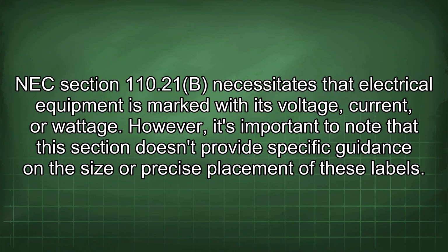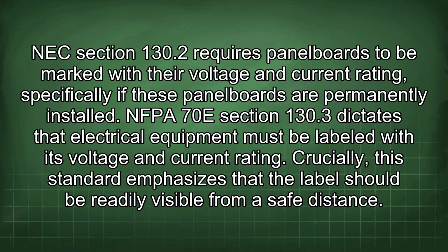NEC Section 110.21b necessitates that electrical equipment is marked with its voltage, current, or wattage. However, it's important to note that this section doesn't provide specific guidance on the size or precise placement of these labels. NEC Section 130.2 requires panel boards to be marked with their voltage and current rating, specifically if these panel boards are permanently installed. NFPA 70E Section 130.3 dictates that electrical equipment must be labeled with its voltage and current rating. Crucially, this standard emphasizes that the label should be readily visible from a safe distance.